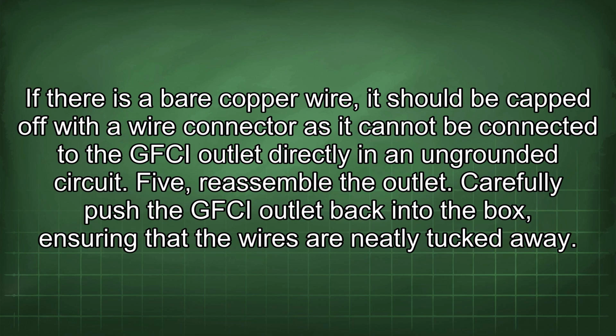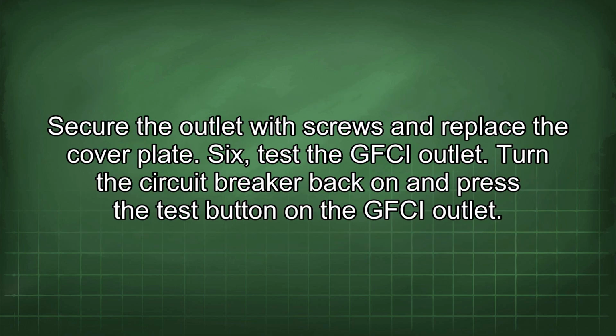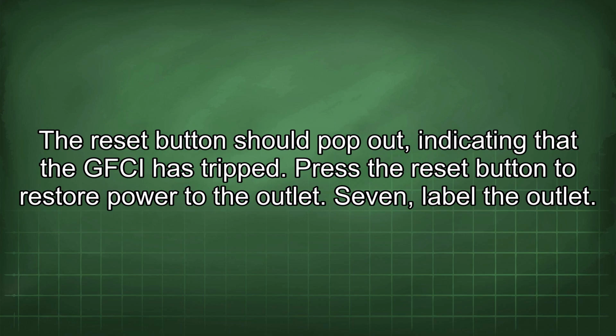5. Reassemble the outlet. Carefully push the GFCI outlet back into the box, ensuring that the wires are neatly tucked away. Secure the outlet with screws and replace the cover plate. 6. Test the GFCI outlet. Turn the circuit breaker back on and press the test button on the GFCI outlet. The reset button should pop out, indicating that the GFCI has tripped. Press the reset button to restore power to the outlet.